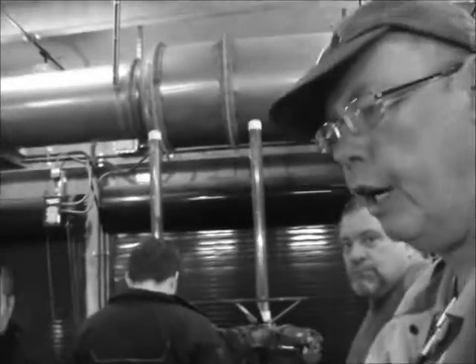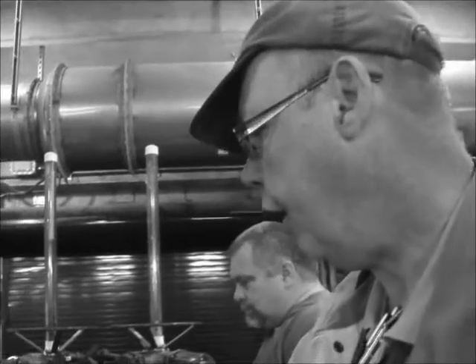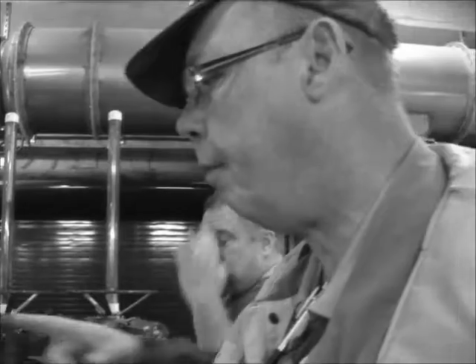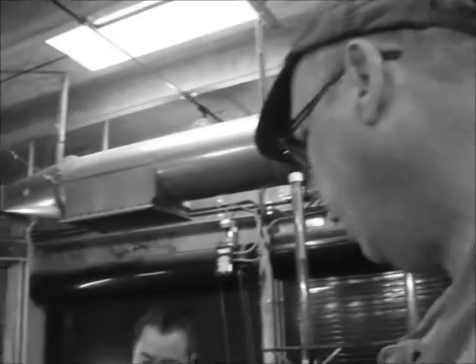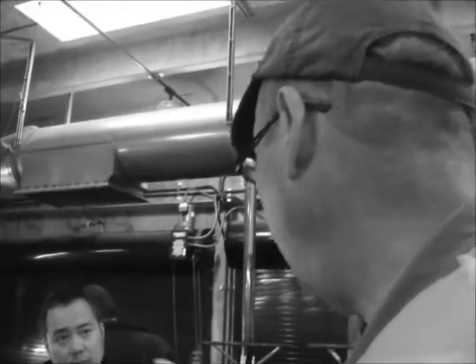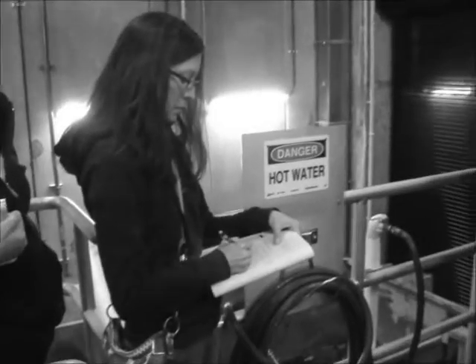These hoppers here have a screw conveyor at the bottom of the hopper that actually agitates the screens. And then it runs through a compaction zone, which squeezes all the water out. Then the screens get dumped right into these. Either one of those is where the screens get dumped. Good.